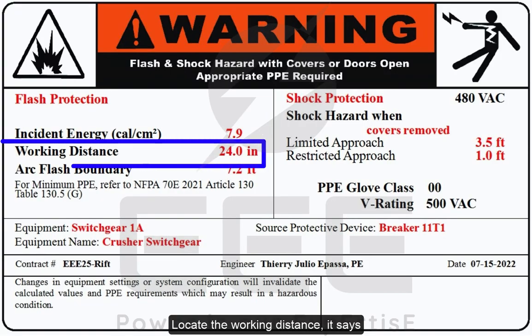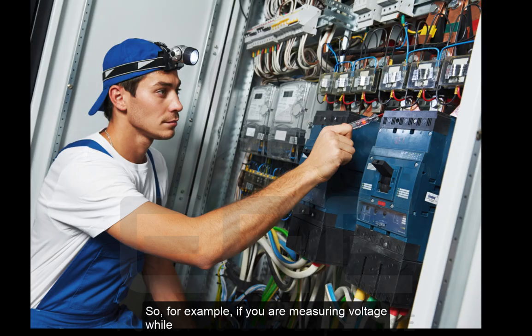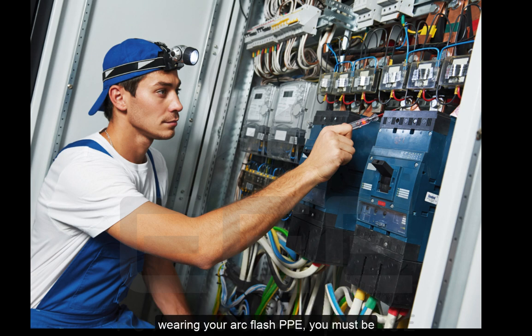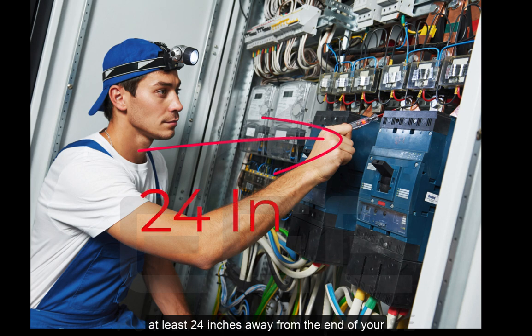Step 4. Since the label has incident energy, the standard requires us to have working distance data on the label. Locate the working distance. It says 24 inches. No matter what you do, your chest and face must be at least 24 inches from the potential voltage source. So, for example, if you are measuring voltage while wearing your arc flash PPE, you must be at least 24 inches away from the end of your meter lead.